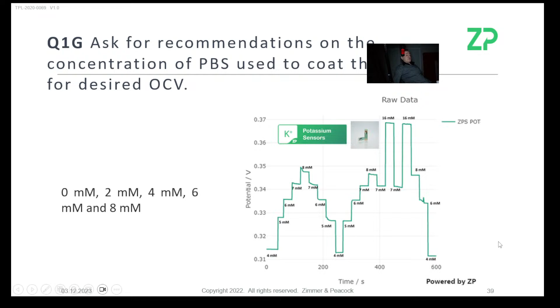In most clinical samples, you're not at 0 millimolar. You're at something like 0.01 millimolar or 0.1 millimolar. It's just a historical accident. But that said, ignore the 0. Then they had 2.7 millimolar. When I look at this, let's look at each one in line. A little bit of drift there. This one comes up and plateaus. This one is solid. This one's solid. This one's solid. This one's solid. A little bit of a drift downwards there. A little bit of a drift downwards there.